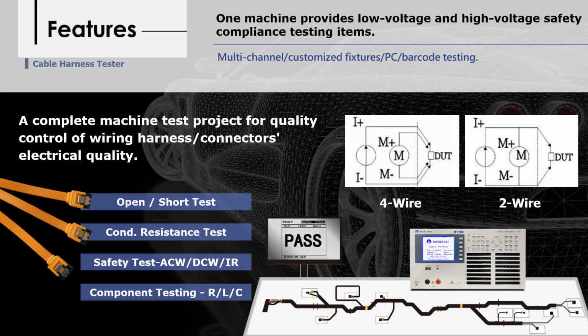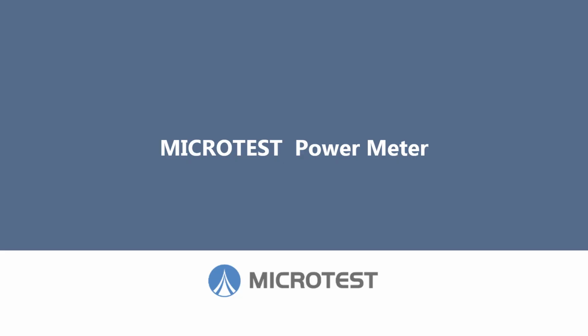If your wire connectivity product falls into a low resistance category, almost in the milliohm range, it's recommended to choose the 4-wire measurement machine. The wire tester offers multi-channel customized test fixtures, the option to purchase PC connection software, and barcode scanning test. Now let's explore the power meter.